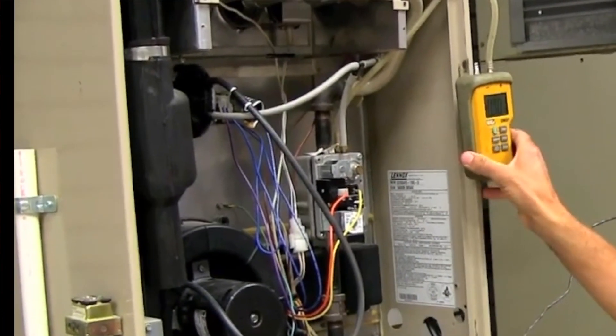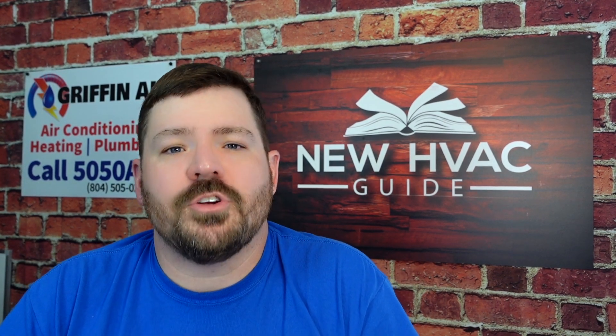The main issue is I see heating and air techs all the time who repair and install things and don't even own a manometer. They don't check gas pressures when installing and create these issues on their own. Because of the problems incorrect gas pressures can cause, I would say if you have any gas appliance in your home, do not go to sleep tonight without getting a carbon monoxide detector installed. I'll put a link below to my favorite one, but any hardware store, Walmart, or Target will have one.